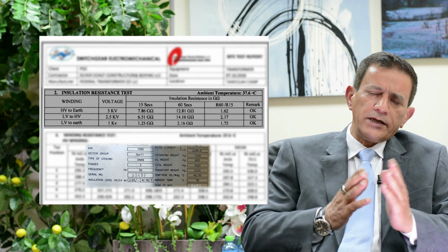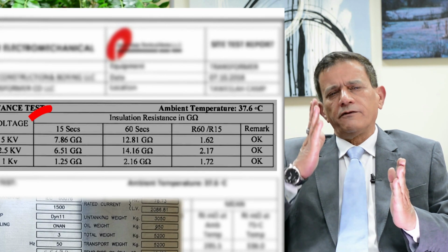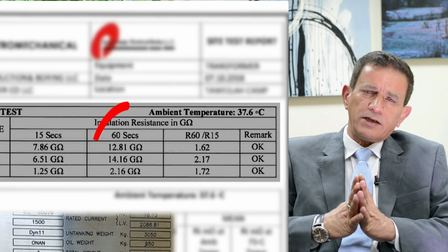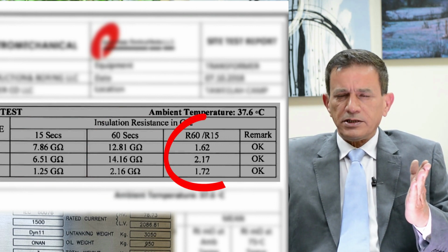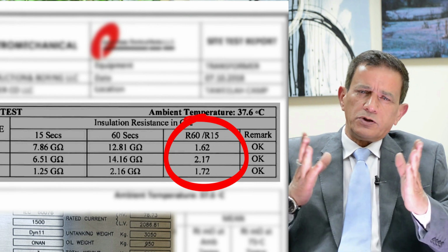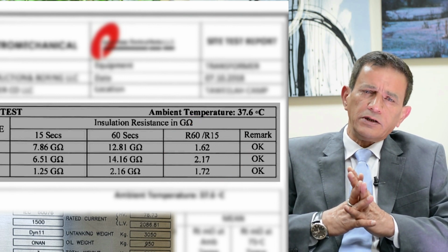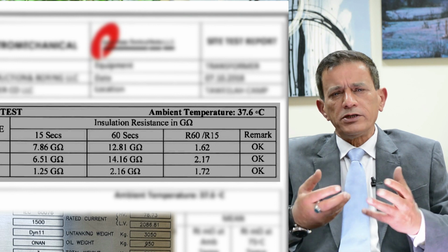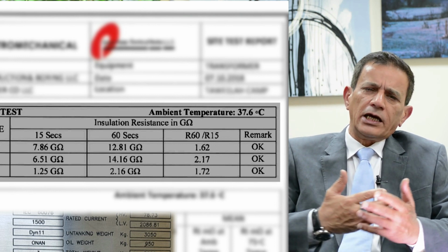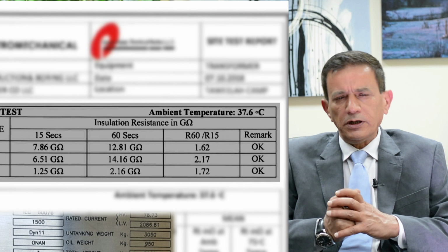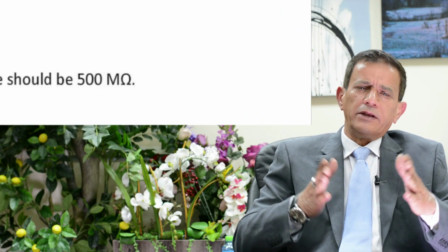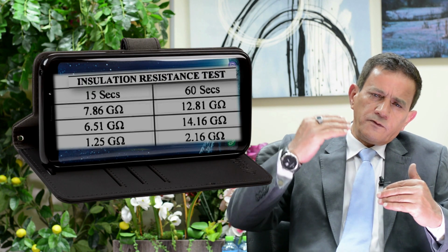And we can see from the results that we took the readings after 15 seconds and then after 60 seconds. Then we divide the 60 seconds reading by the 15 seconds one, which is normally called the polarization index, to take into consideration the components that we mentioned in the beginning, like the capacitive, surface, or polarization component. And if the insulation resistance is more than 500 mega ohm, the results will be satisfactory. But as we can see, the results obtained are in the range of giga ohms. So this transformer will pass the test.